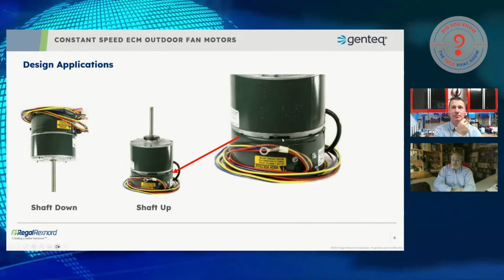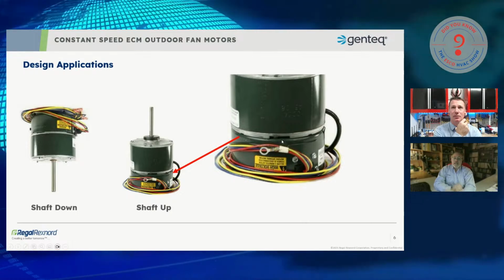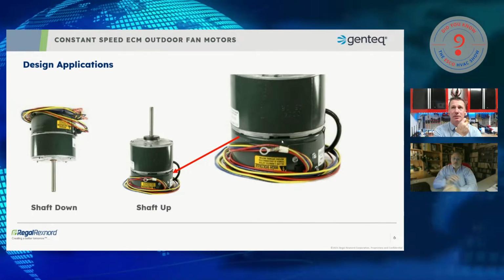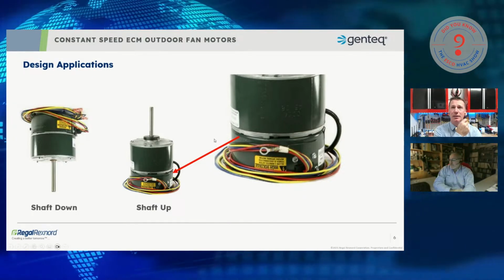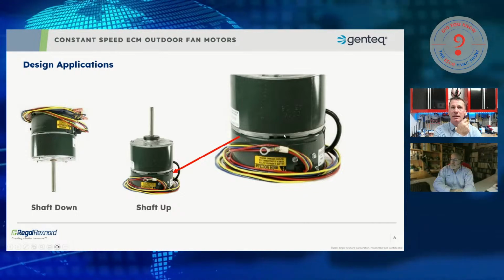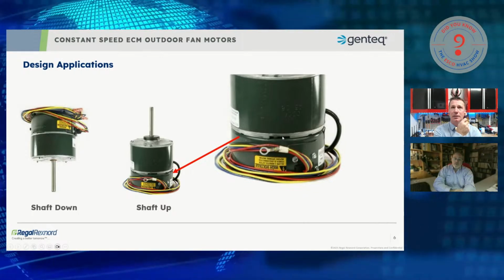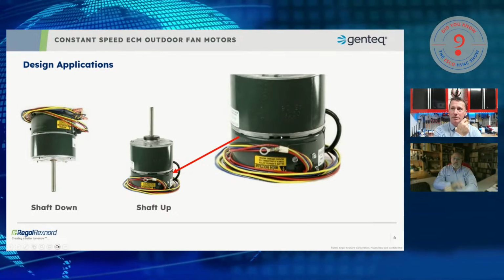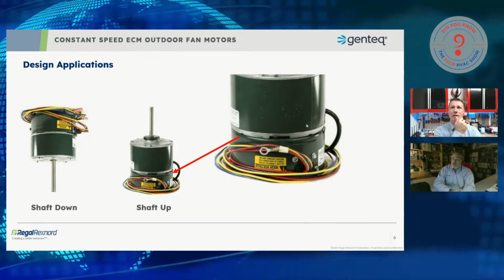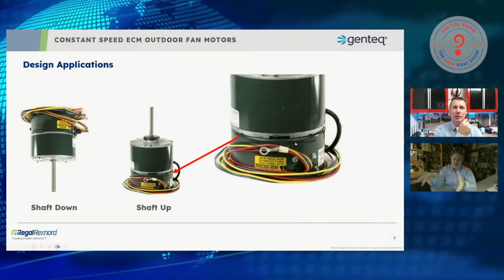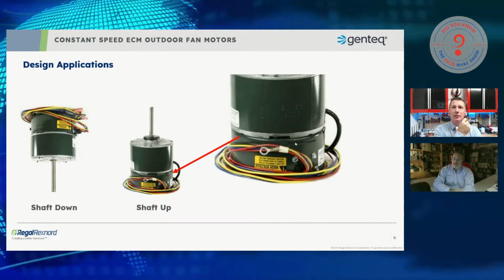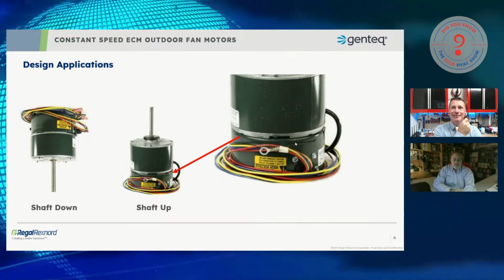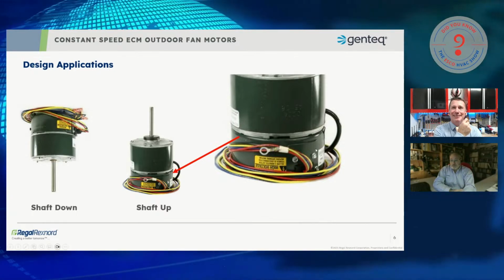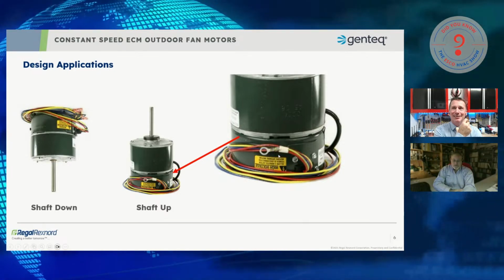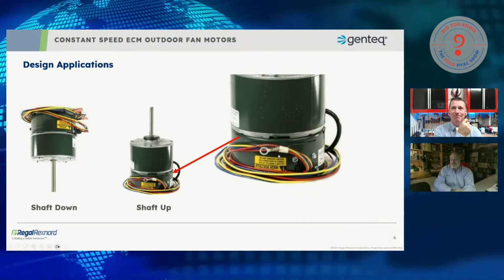And we do that again so that the molded portion of the can is facing up so that water can run off that. If we left it mounted this way, we would have a seam between the motor and the control where water could come in and literally pool inside the control. By flipping the control, now that water runs off. All that's on the bottom of that is simply a dust cover.